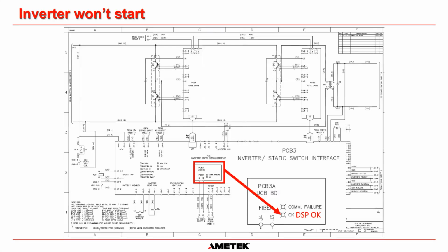One thing that we talk about when people come to our class in Stafford is in the DPP systems, we have something that's called fast blink, okay? All of our boards have a UCB, which is a universal communication board on it. And we connect our fiber optic cables between each board, and that is how all the data transfer is done within the system. If the signals for these boards did not get sent correctly, you will not get fast blink. And that is the DSP OK light, okay? And it should blink very fast.